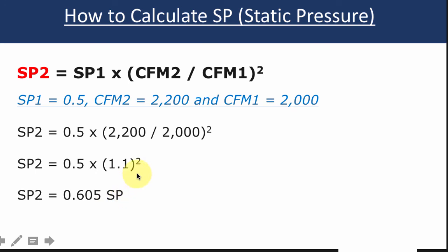And static pressure, same thing. To get the new static pressure, you use the existing static pressure times your new CFM over your old CFM squared. So once again, put all those values in, do the calculation, and you get 0.605.